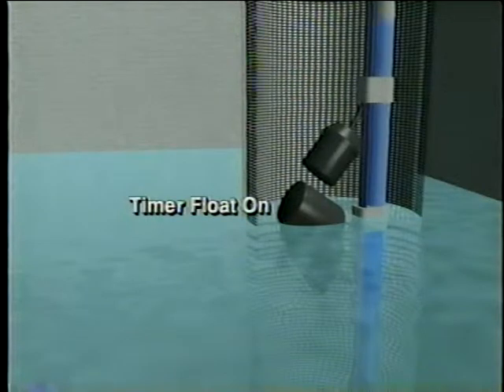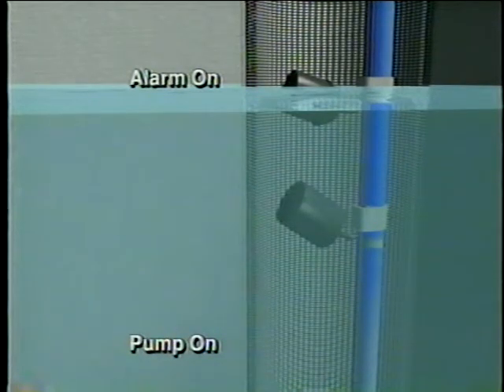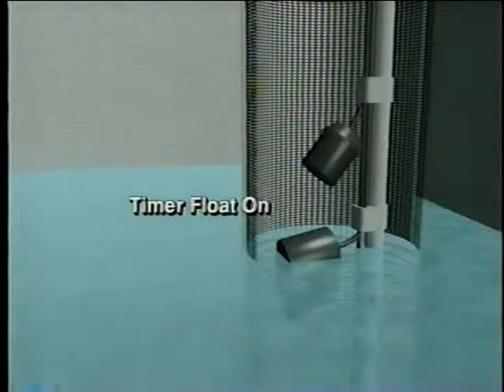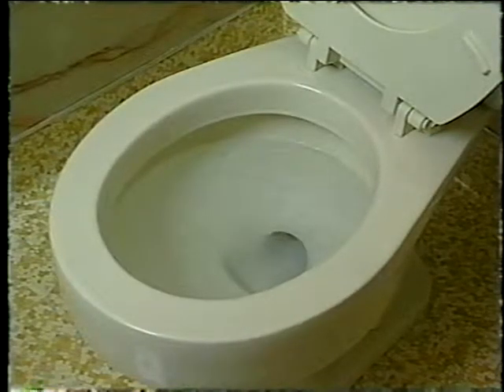Occasionally, when more sewage enters the tank than it can store, the liquid level rises to the top float, which immediately turns on both the pump and the high-water alarm. The pump continuously disperses effluent to the sand filter, quickly lowering the level in the septic tank until the high-water alarm float drops to its off position — usually within two minutes — and the alarm shuts off. Infrequent short-term high-water alarm conditions are normally nothing to worry about, especially if they coincide with overnight guests or occasional parties. Frequent and/or continuous alarms usually indicate a problem with the system. They can be caused by leaky faucets, a running toilet, or too many loads of laundry in a short period of time.